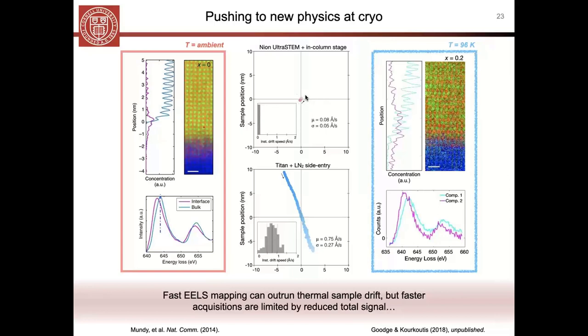Here's that same sample position plot, but now you can see that the mean instantaneous velocity on this in-column stage is roughly an order of magnitude slower than the instantaneous velocity we have once we move to both side-entry, and especially to these in situ cryogenic conditions. That difference in velocity and time scale is really what's limiting our measurements under cryogenic in situ conditions at this point.